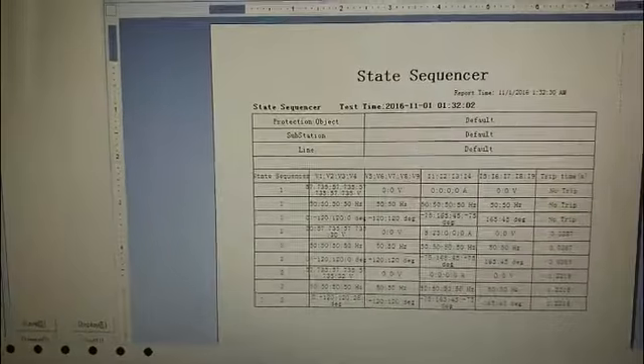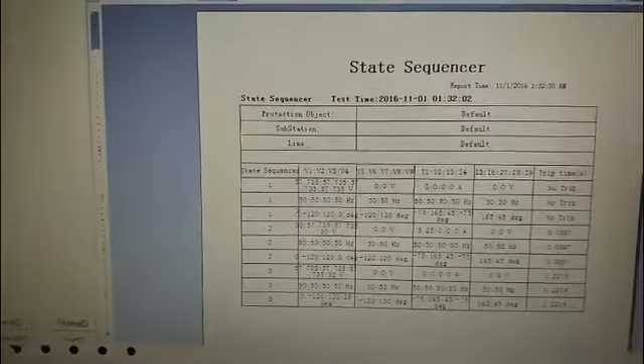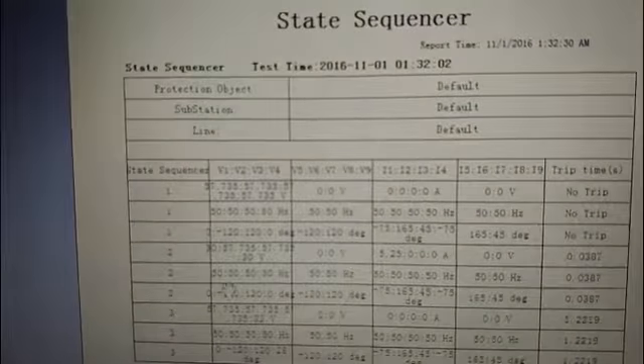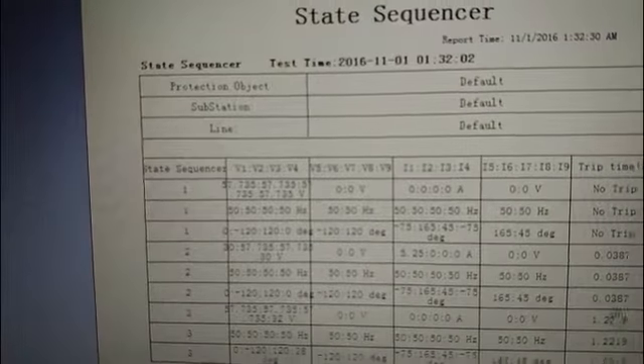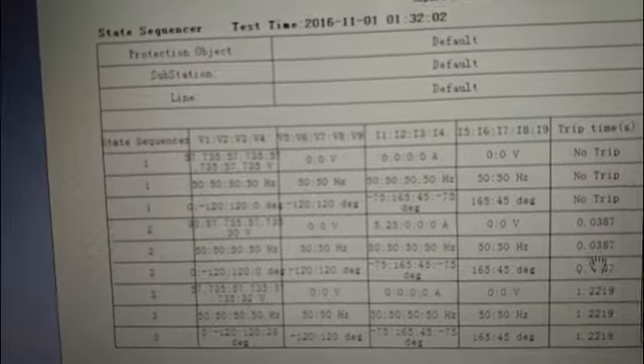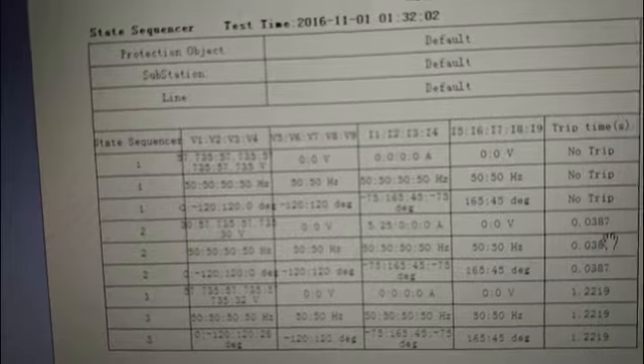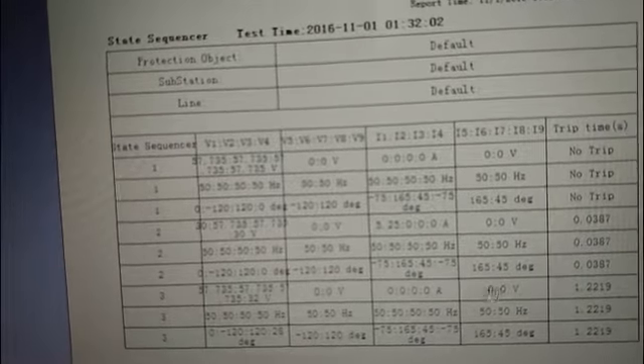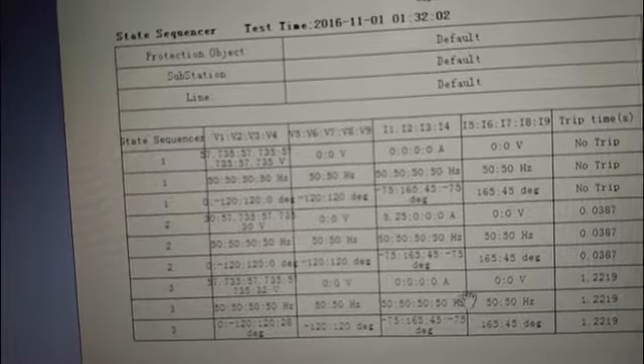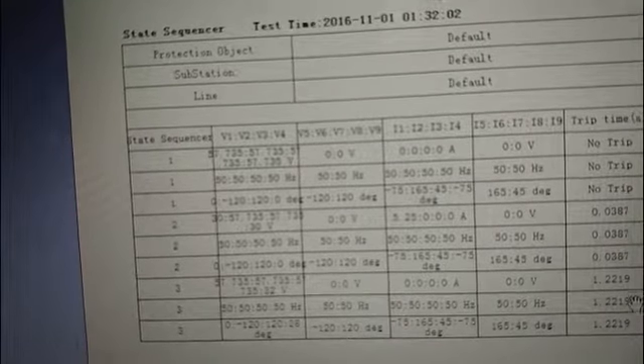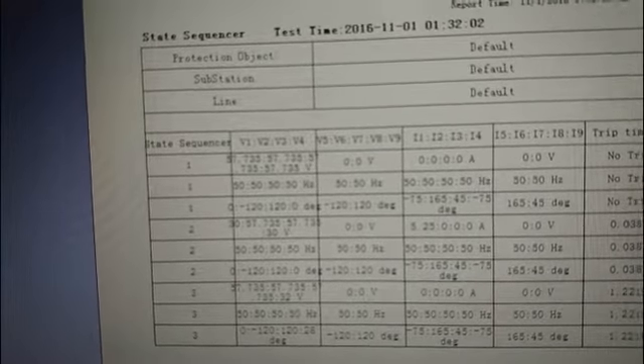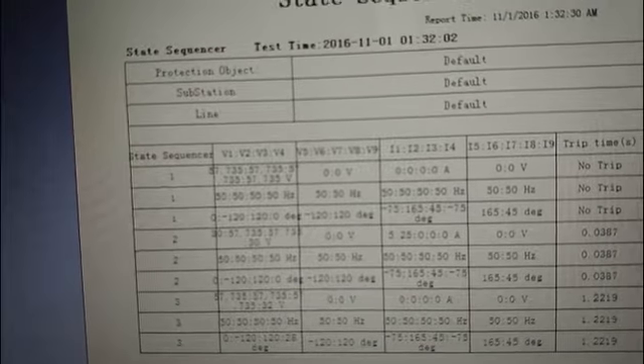Let's look at the test results. The trip time is 0.0387 seconds at the second status. Reclosing time is 1.2219 seconds. It is very close to the setting value.